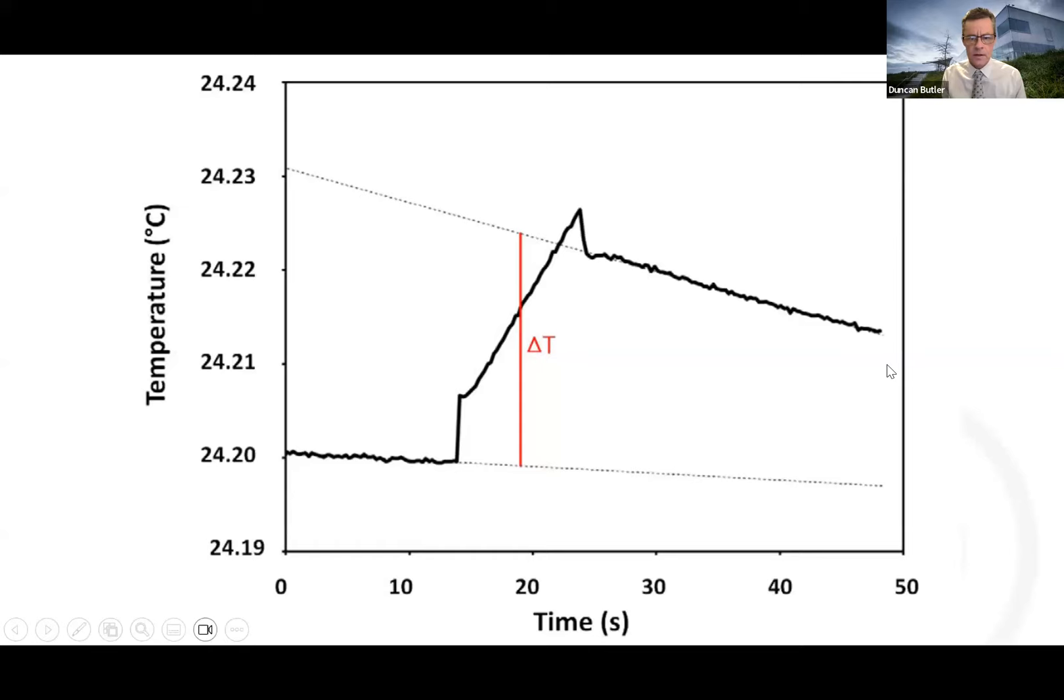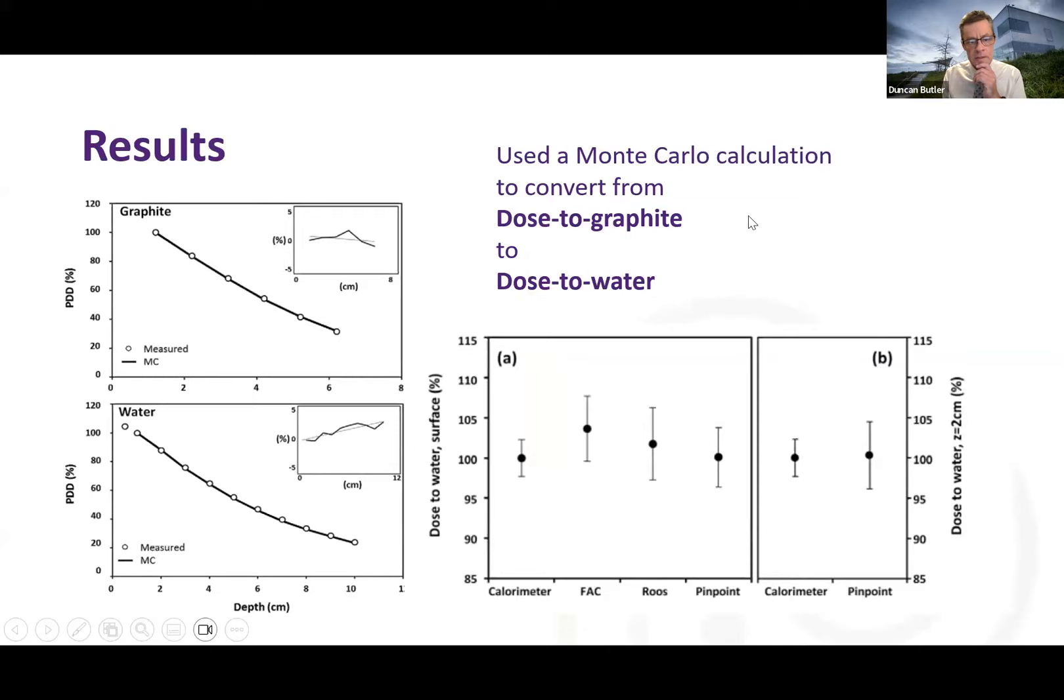And finally, the other difficult thing is this is a graphite calorimeter and we want dose to water. So we get that by modeling the depth dose in graphite, the depth dose in water. And if they agree, which they do in those two plots, we argue that the Monte Carlo can calculate the ratio between the two. And that's what we used here. And you see the calorimeter and the pinpoint actually agree really well in dose to water.